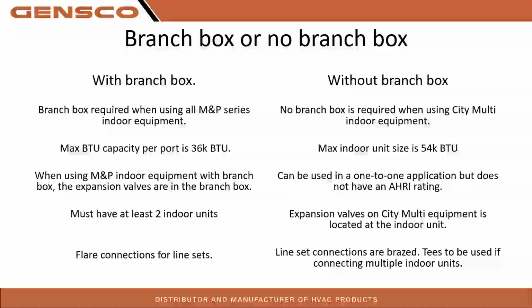Can be used as a one-to-one application if you're doing city multi. So if you are looking to just do one big PVFY 54, you can do it as a one-to-one. Just be aware that there is not an AHRI rating for that anymore. On the M&P with a branch box, if you're using a single SVZ that is at least meeting the minimum requirements at the heat pump, Mitsubishi does allow you to do an SVZ as a one-to-one on a Smart Multi heat pump, just FYI. But again, no AHRI rating for that. So if you're trying to get any rebates or anything like that, that is not going to be available for those.